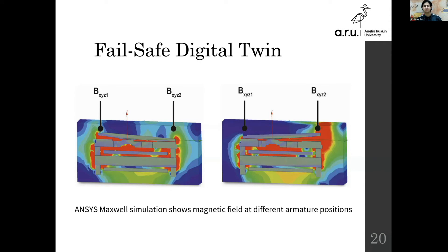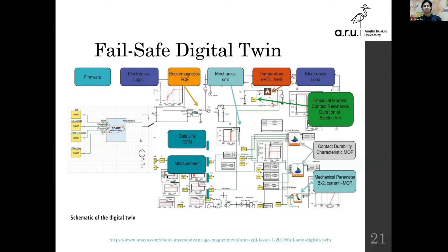ANSYS ran a Maxwell simulation to show the magnetic field at different armature positions, allowing them to gauge after how many cycles the relay would tend to fail. Based on that data, they created a digital twin so that in real time they can monitor all aspects coming into the system and know exactly when something can go wrong. If failure is approaching, the relay can simply be replaced during the next maintenance run or when the production line is not in use.